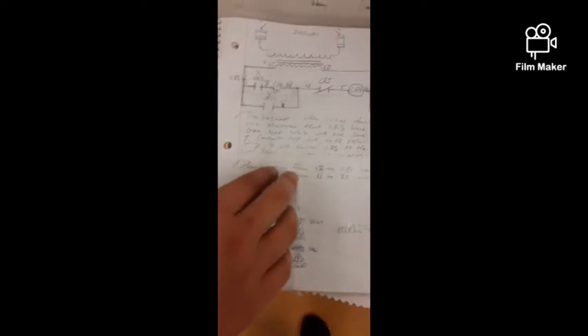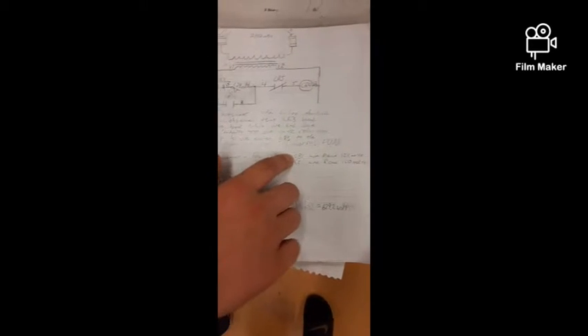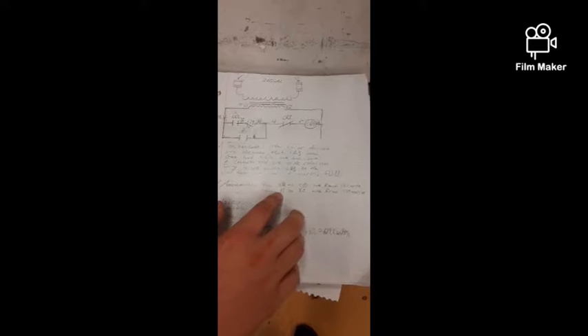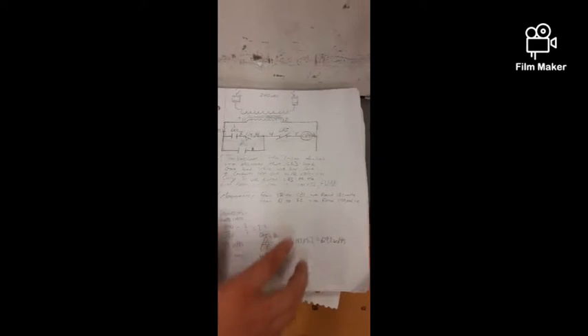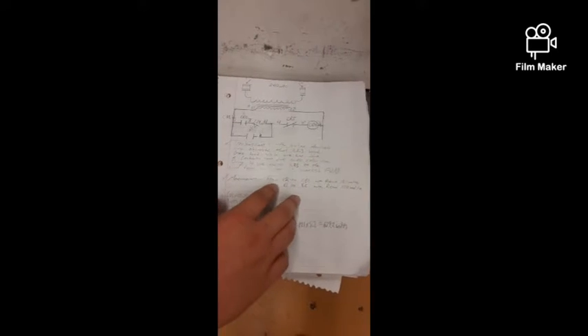So the measurements we took were from X2 to circuit breaker 1, and we read 121 volts. That's to be expected. And then from X1 to X2, we again read 120 volts. That's to be expected because the transformer is converting 240 volts to 120.